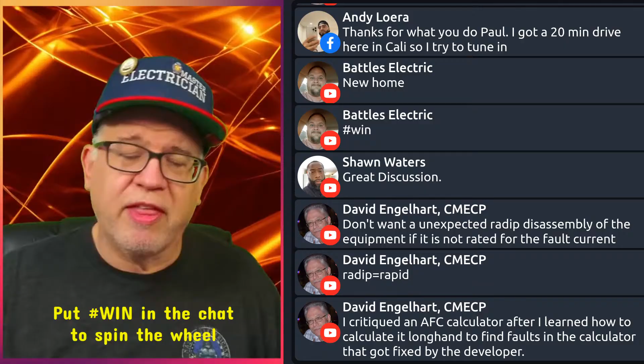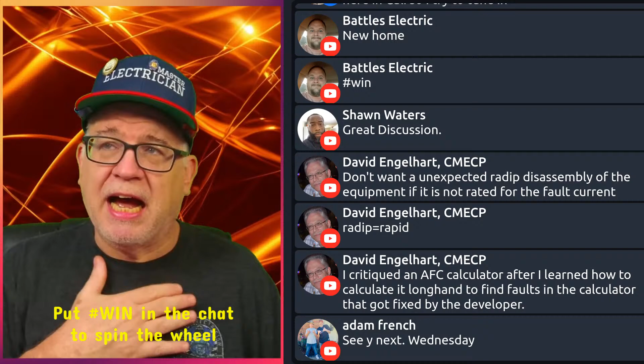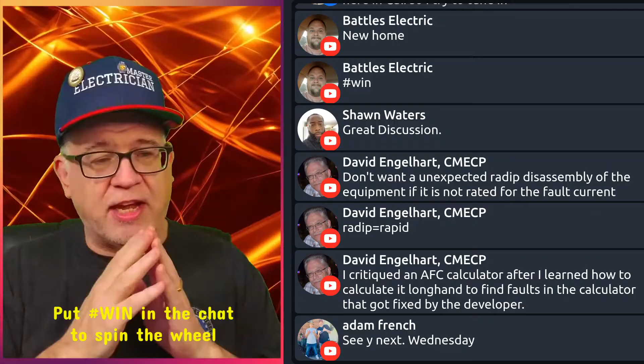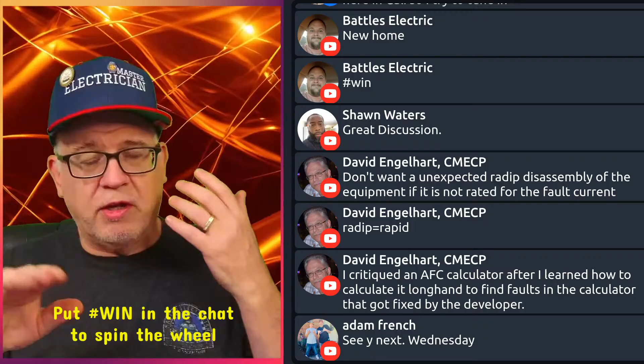Yeah, David, you do plan review. I would never do that for my customers because it increases the liability to my jurisdiction. I never messed with it. I just wanted them to provide me with the numbers, and as long as that engineer stamped it, I was fine. I never got into calculations like that because it made my jurisdiction liable. I stayed away from trying to calculate the impedance from point A to point B because our lawyers did not want us to do that. So we just verified what the equipment rating was and what the available fault current was at the source, and if they say downstream that it's okay, I'm okay with it. The moment I start calculating it, I'm playing the engineer, and I was not a PE.